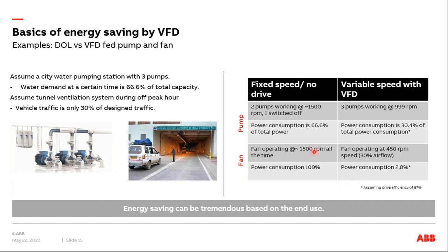Now, instead of having this fixed speed system operating at the rated speed all the time, which consumes 100% energy, with a VFD system you could operate the fan at 450 RPM to give you this 30% airflow, and you can see the dramatic difference in the power consumption. You are only using around 3% of the energy. So in this centrifugal system, it's really a no-brainer, I would say, that we should be going to VFD systems. We can talk about some drawbacks of having VFDs, but I think the benefits outweigh the drawbacks by a significant margin. So this is one example.